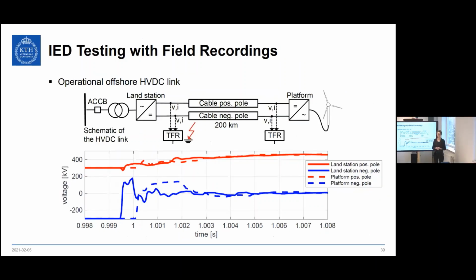And that's perfectly feasible if your AC grid can handle that, but if not, and if it's a very large grid, then you can't do that, basically. Yeah, indeed, and I know some co-authors on your papers have views on that too. So that's the extreme version: collapse the whole DC system when there's a DC fault, isolate, and come back up, and as you say, you have to be sure your AC system can survive that momentary outage.